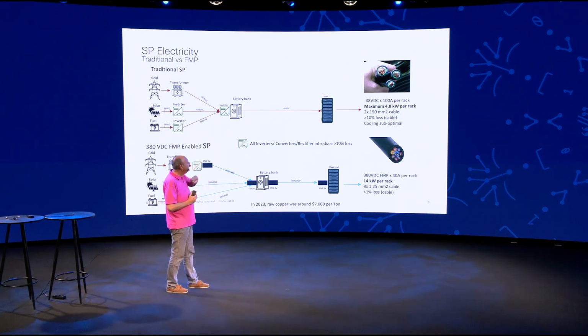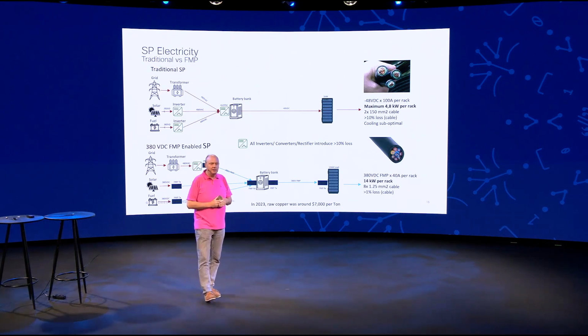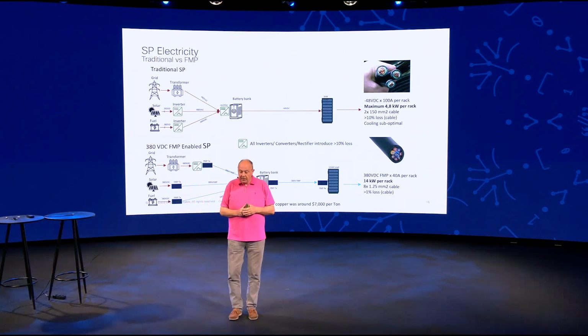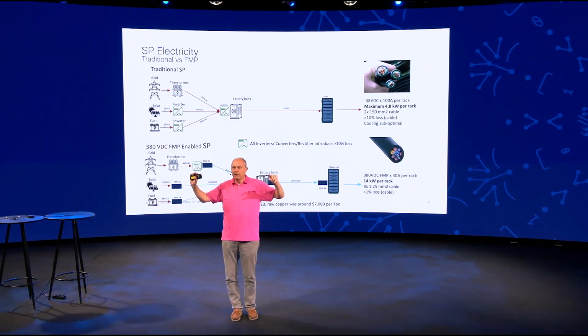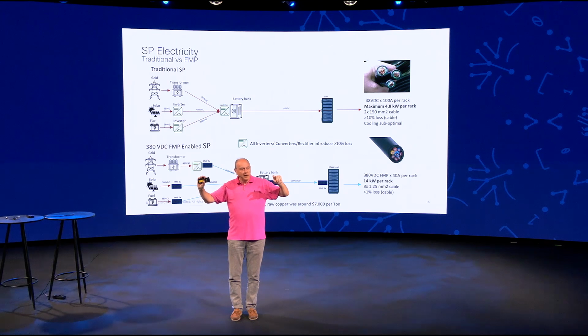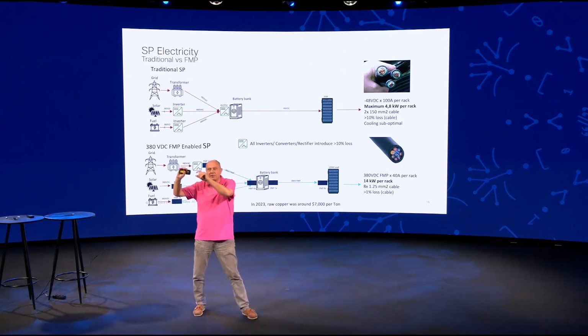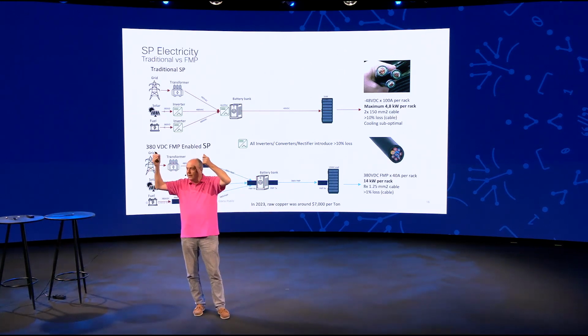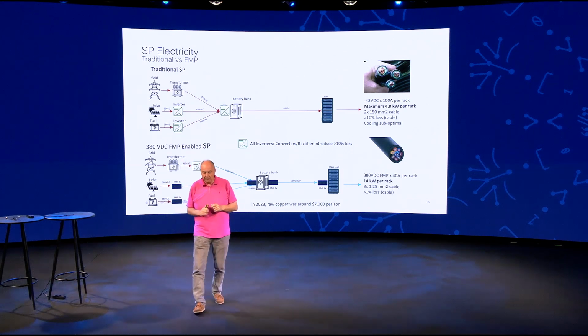For all of those reasons, this is super inefficient. Because it's limited to 4.8 kilowatts, and today in a single rack unit you could consume that energy, you basically have a real estate problem as well, because now in one rack you have one device that's one rack unit, and then you can't plug anything else into that rack. Everything else is empty, and then you have another rack with one rack unit of equipment. That's a big problem too.